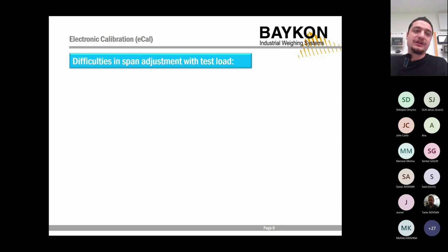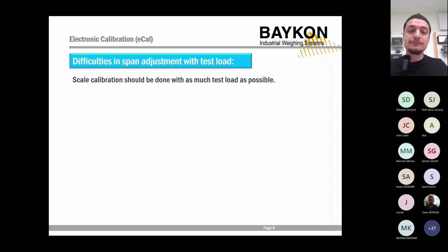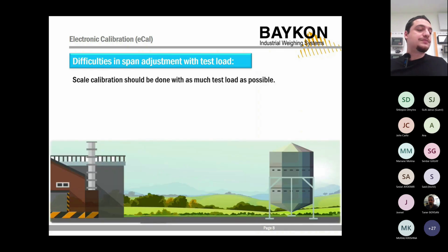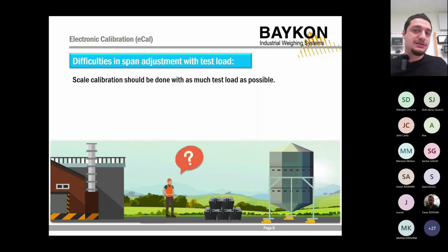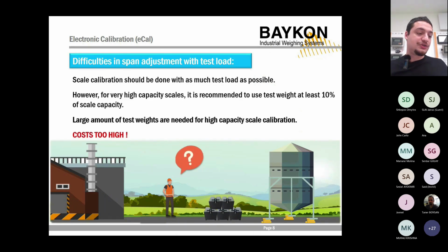And since we are an industrial weighing equipment producer, the feedback that we got from the field, the most popular problems, you might say, are as follows. One of the biggest problems is the fact that you need weights to perform manual calibration. As I said, for scales that weigh 100, 150, 200 kilograms, finding that much weight to calibrate the scale is not that hard. But however, as you can also see here, imagine a tank scale that might weigh 50 tons, 100 tons, 500 tons even.